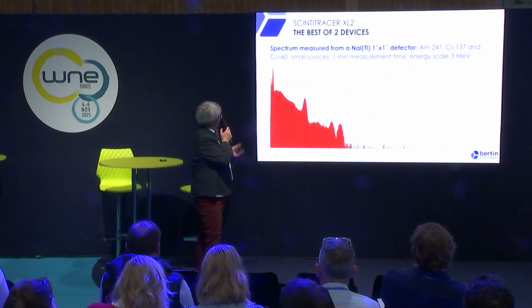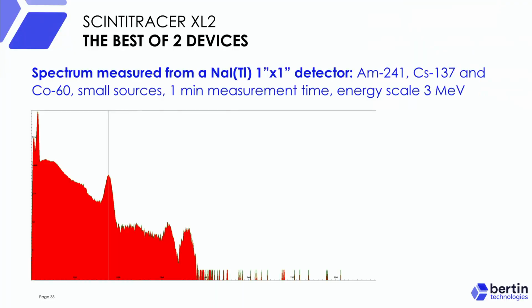Here, a small spectrum. You easily see the peak of americium, the peak of cesium, and the 2 peaks of cobalt. This is a real spectrum given by the new device, with a small source in 1 minute measurement time. Linearity, very important when we're talking about norms.